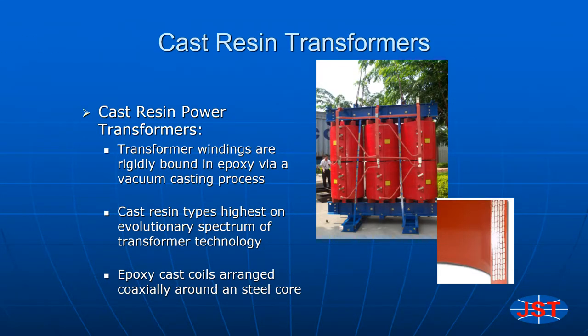Now I would like to shift our focus and specifically talk about cast resin transformers. Shown here is a core and coil assembly along with a cross section of the molded coil. As you see, the transformer windings are rigidly bound in epoxy resin. This core and coil assembly has both a high and low voltage coil for each phase. These coils are coaxially arranged around the steel core and both are vacuum cast.